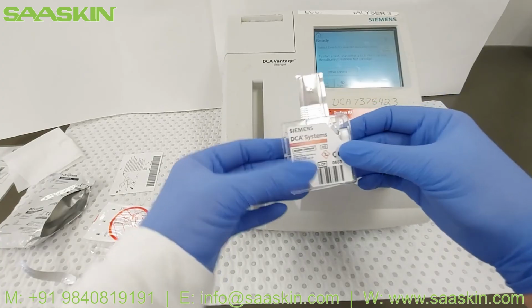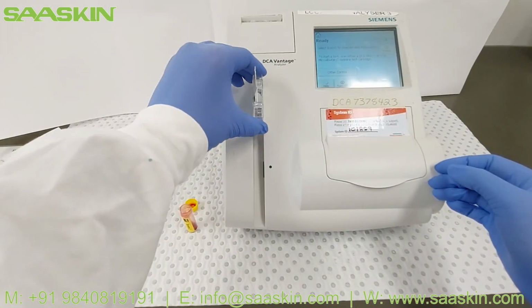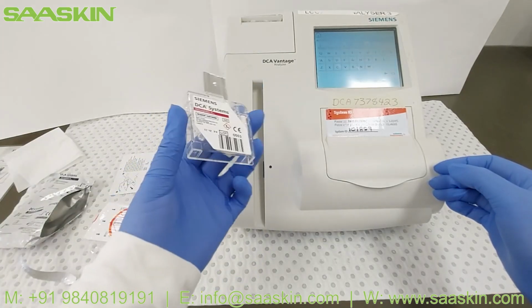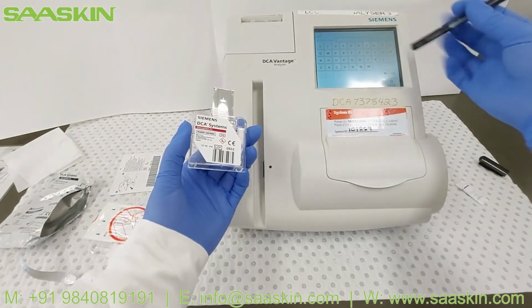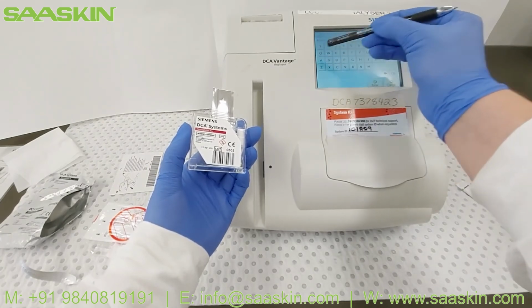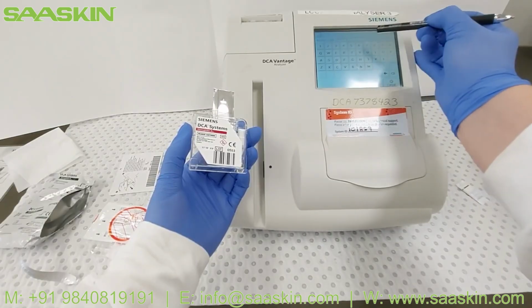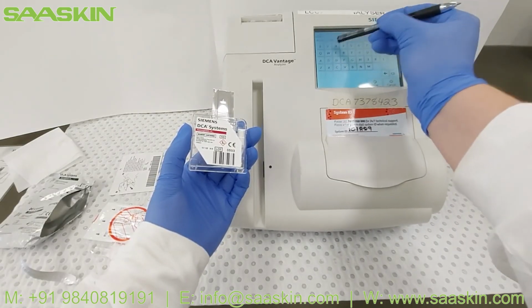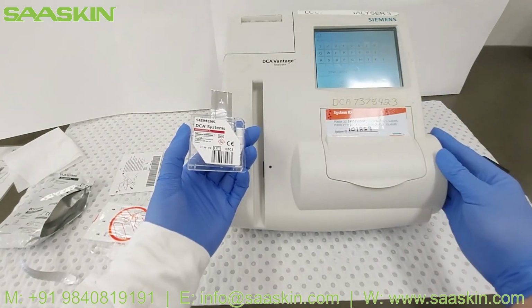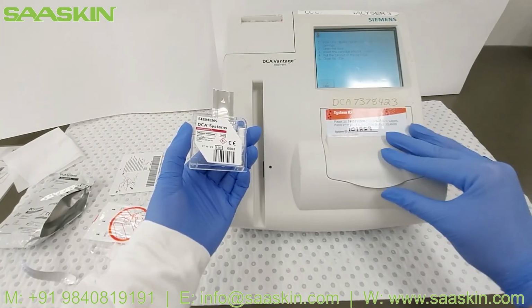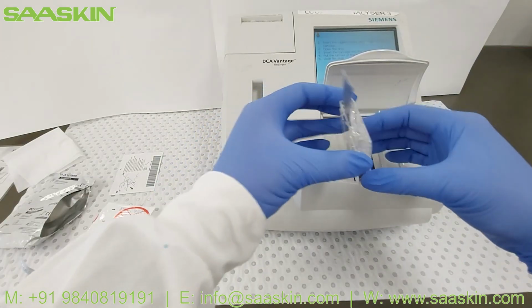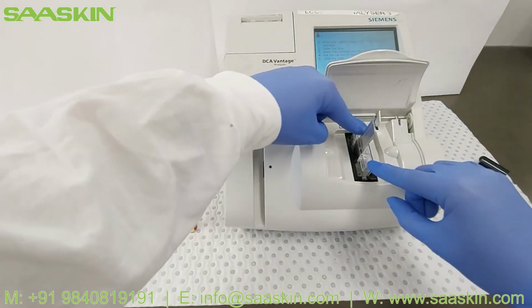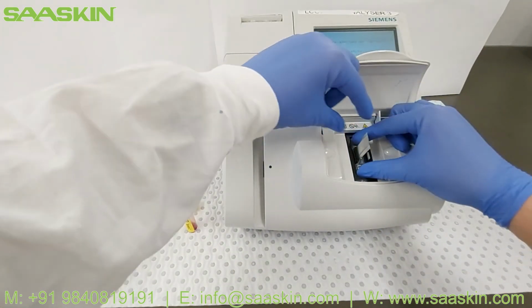Scan the reagent cartridge and capillary tube assembly in the onboard barcode reader. Now enter the access code using the display screen, either with your finger or with the stylus. The access code will be an individual code for each user that will be set up in advance. Once the access code is accepted, insert the reagent cartridge into the reagent cartridge compartment with the barcode facing to the right until an audible click is heard.